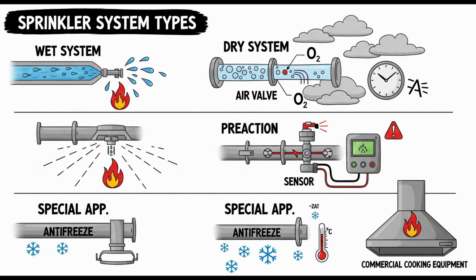Firstly, and very importantly, the use of any antifreeze solution must comply with state and local health regulations. This is mainly about preventing contamination of the potable water supply. Right, you don't want antifreeze getting back into the drinking water. Absolutely not. A major technical restriction is that antifreeze solutions are not permitted in ESFR, early suppression fast response, sprinkler systems, unless the specific ESFR sprinkler head has been tested and is listed for use with that particular antifreeze solution.